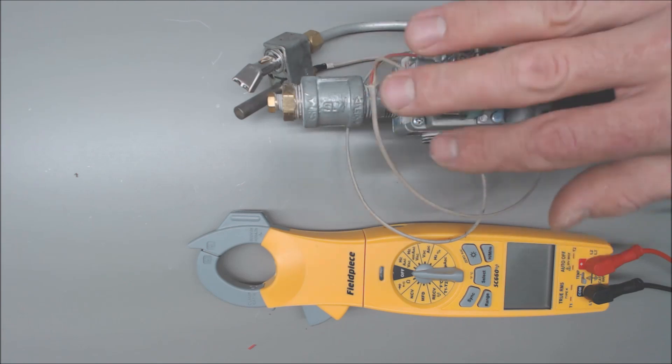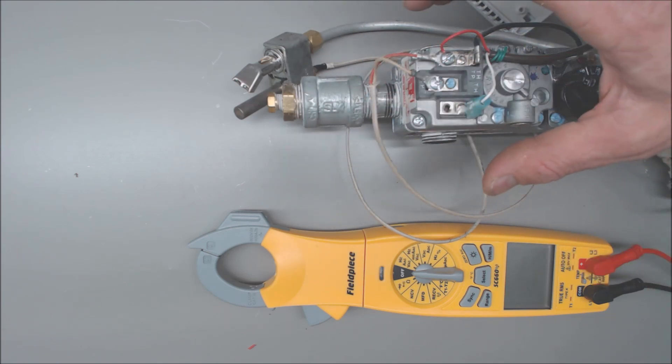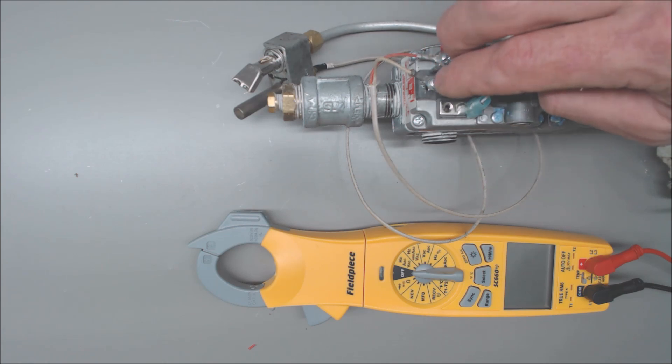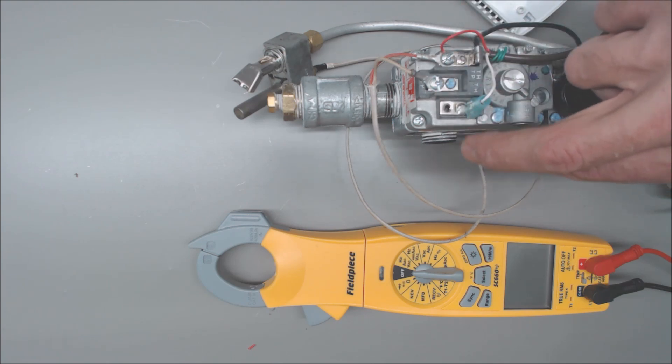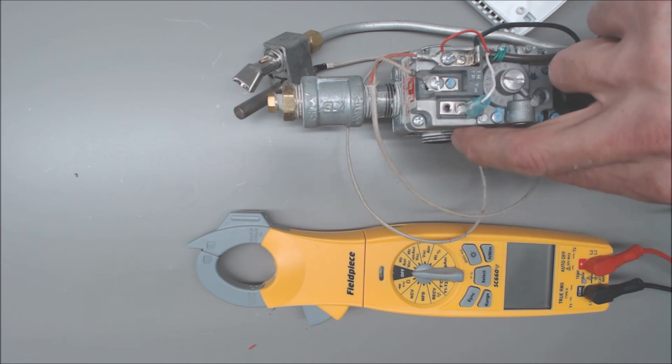You'll see a voltage drop of maybe 20 millivolts or maybe even 100 millivolts, and that's a big deal. If this needs at least 50 to 60 millivolts DC and preferably 100 millivolts DC, your main gas valve actually needs 250 millivolts when powering.